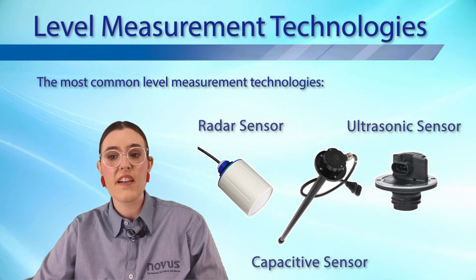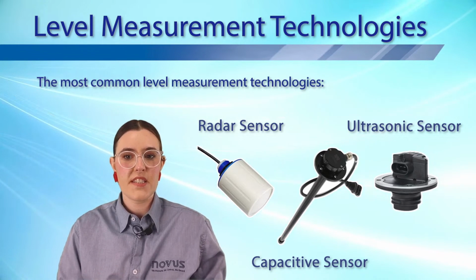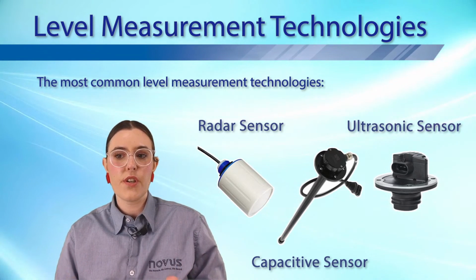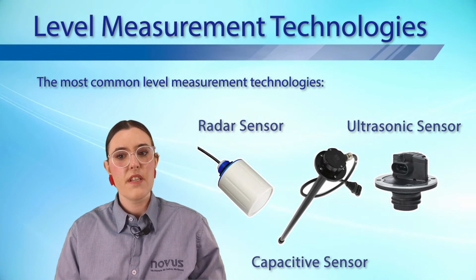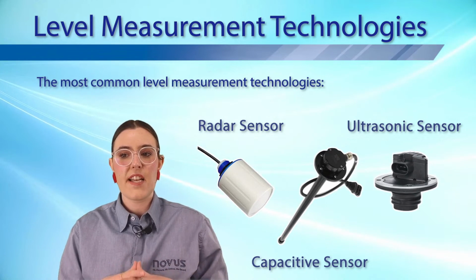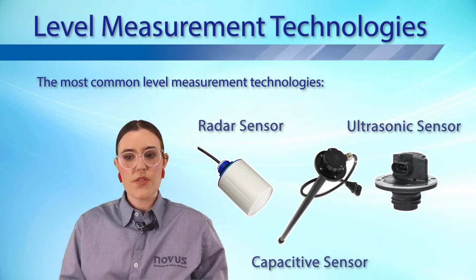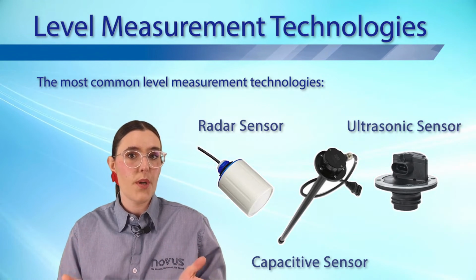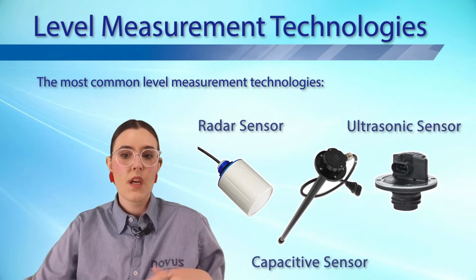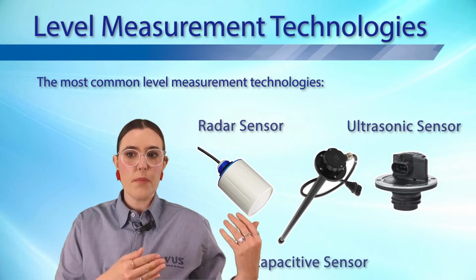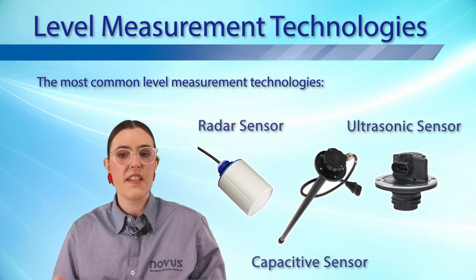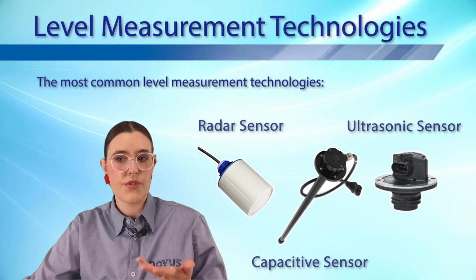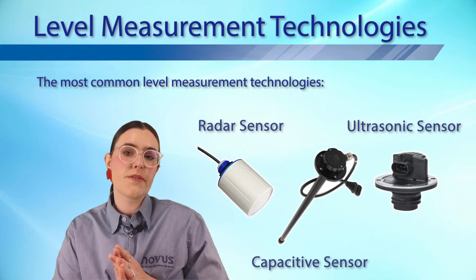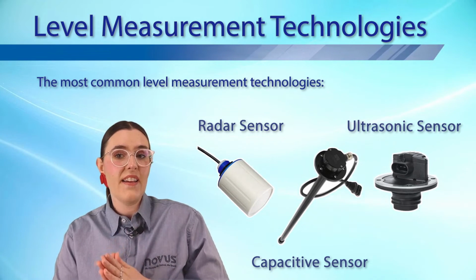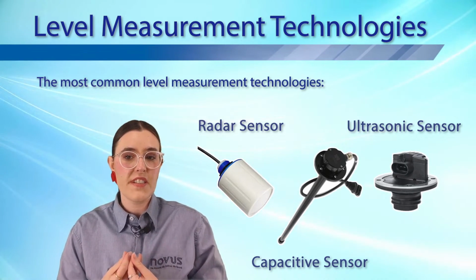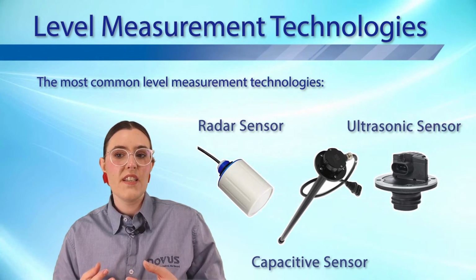Ultrasonic sensors require a higher financial investment compared to capacitive sensors, and they do not meet the material under normal conditions. However, under any movement, they saturate when in contact with the liquid and generate measurement errors or even interrupt the monitoring process. Radar sensors solve the previous problems, but at a much higher acquisition cost than a capacitive or ultrasonic sensor. So the new NOVUS Automation sensor, TL400-I, has some of the characteristics mentioned here and solves these points of fragility mentioned earlier.